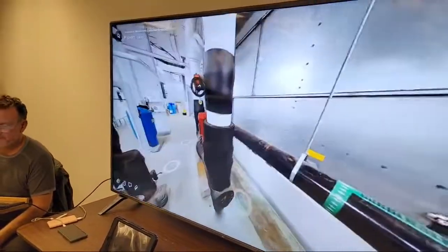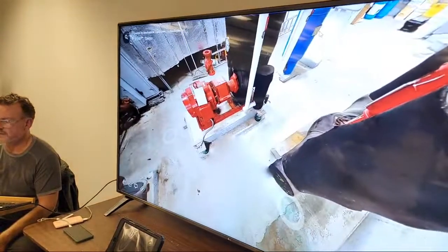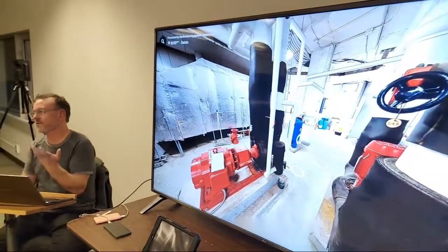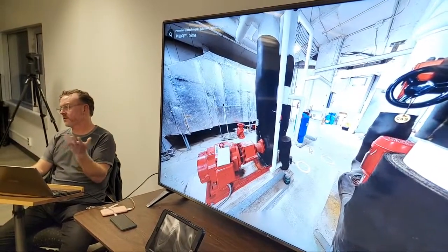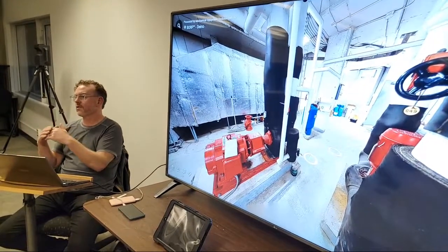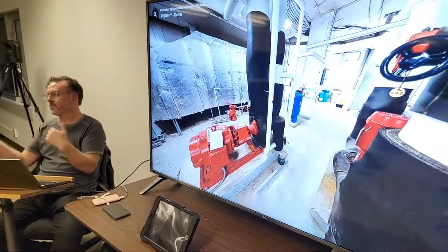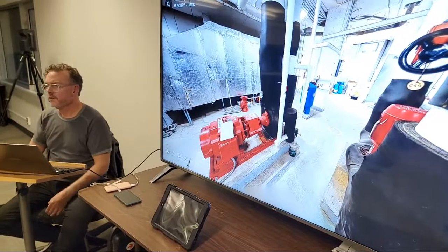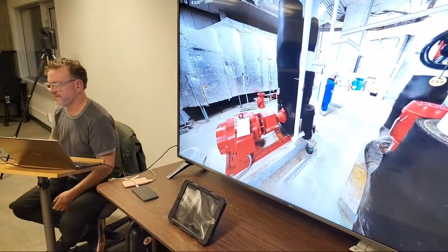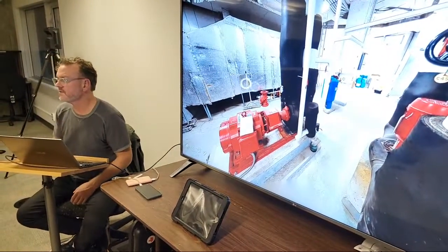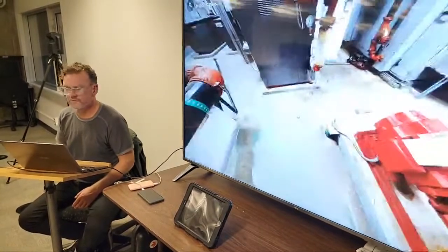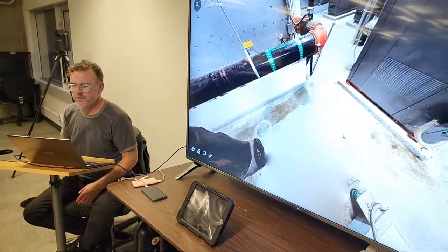They've got a base mounted pump and a vertical inline pump. That's an expansion tank. So an expansion tank is what we use. There's control air devices in closed loop systems. They're the interface between the closed loop and the atmosphere, right? They're also there for the expansion of fluid when it's heated, when it heats and cools, so there's room for that.